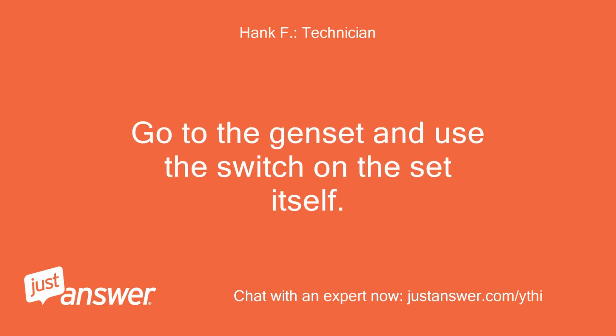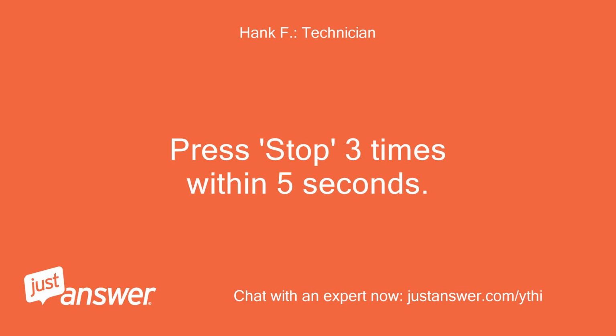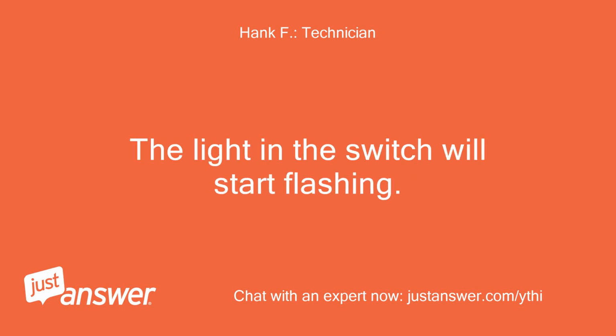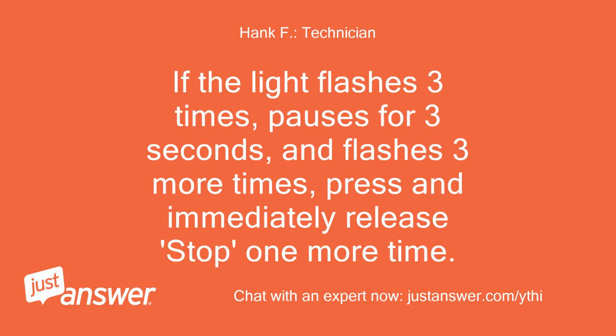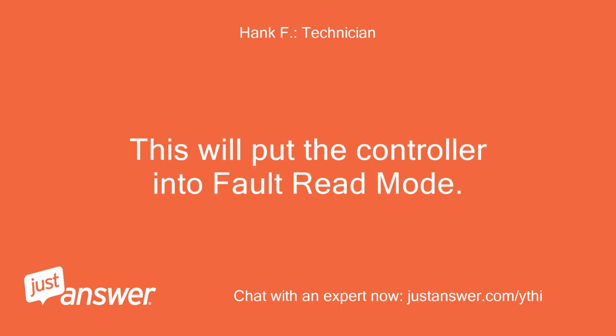Go to the genset and use the switch on the set itself. Press stop 3 times within 5 seconds. The light in the switch will start flashing. If the light flashes 3 times, pauses for 3 seconds, and flashes 3 more times, press and immediately release stop 1 more time. This will put the controller into fault read mode.